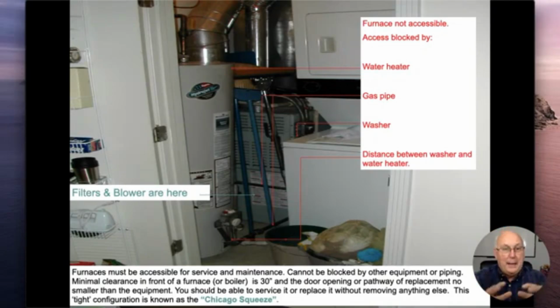So they just compact all the utilities that are in there. But let's use a little common sense here. I've got a gas pipe that's going right in front of that blower compartment door. There's no way for me to get in there without dismantling this whole thing before doing any sort of work. That also goes in front of the return ductwork, which just so happens to be where I get my filter out of there. This filter was never changed since it's been there because it's physically impossible to do so.